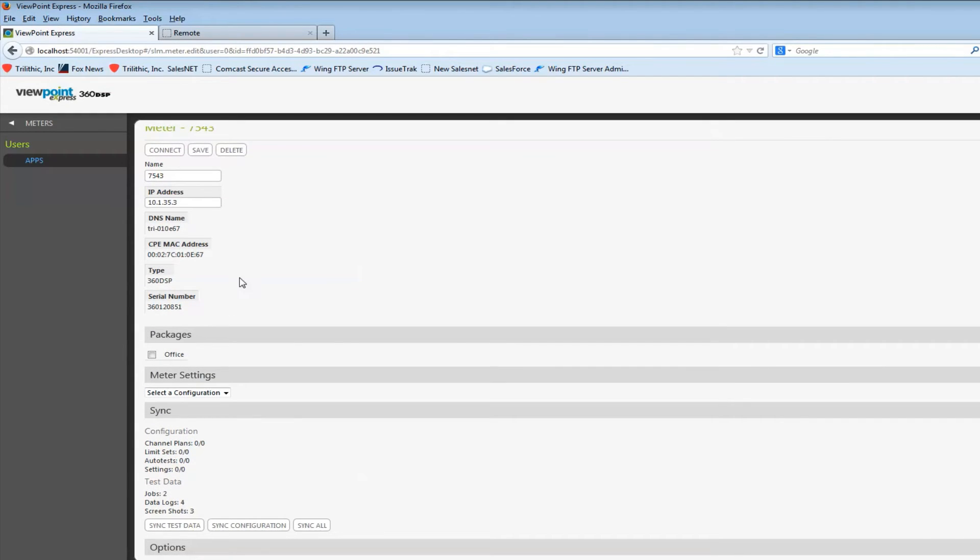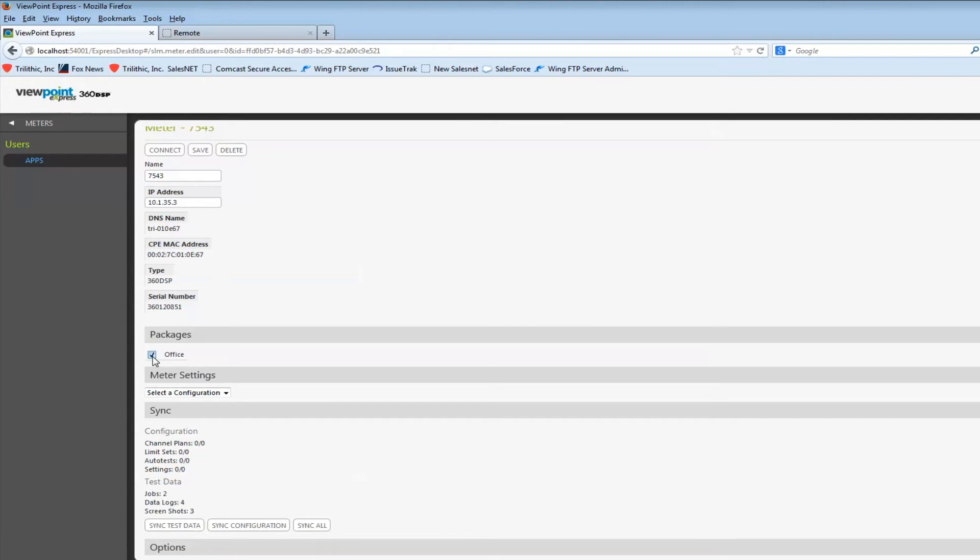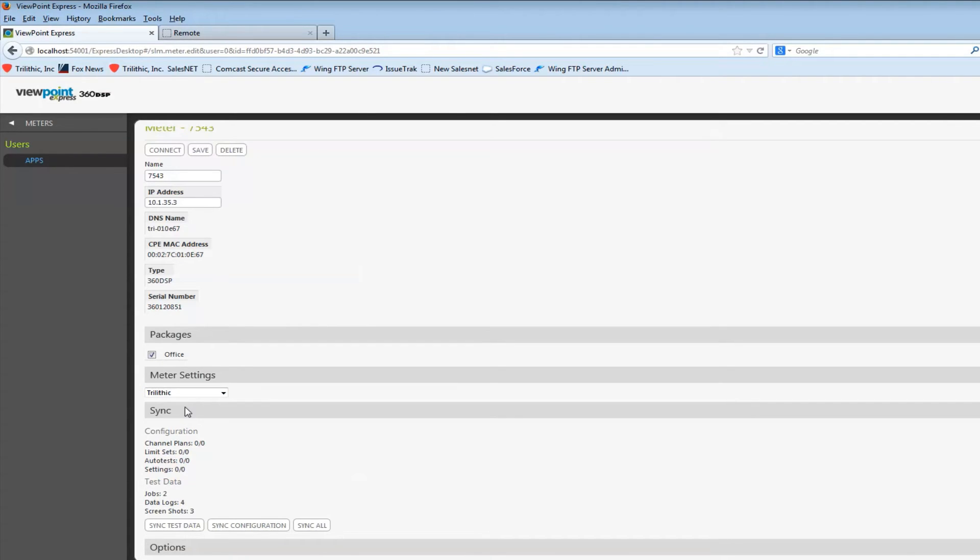Really all I want to do is select the package to transfer to the 360. The package of course has the channel plans, the limit sets, the auto tests, any of that information, and the meter settings. These are the security settings you can configure if you desire for the 360.